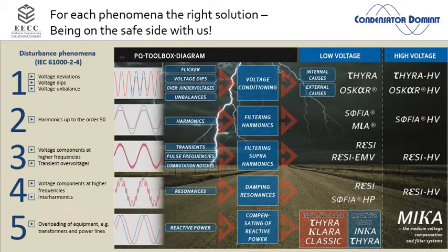What is a typical SMA reactive inverter? Something like 60 kVA, 100 kVA, but there's 100 of them. And they put a lot of high frequency signals onto the grid. That is a very, very interesting phenomenon. The one or the other of you might be confronted in the future, as sunny South Africa wants to utilize the sun, not only for enjoying ourselves, but also for sun power. When you have a solar park with 20 megawatt tripping once in a while, then put a piece of measurement equipment that runs up to 20 kilohertz, and send me the measurement data. Then we might find out why it trips, because they tend to disturb each other.